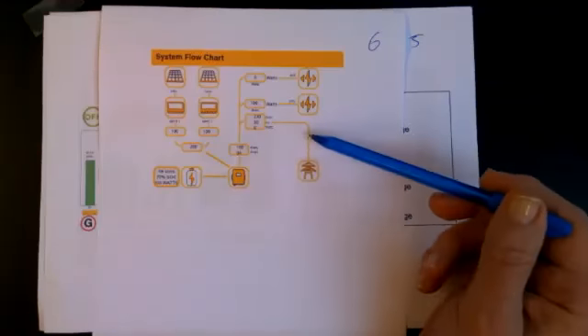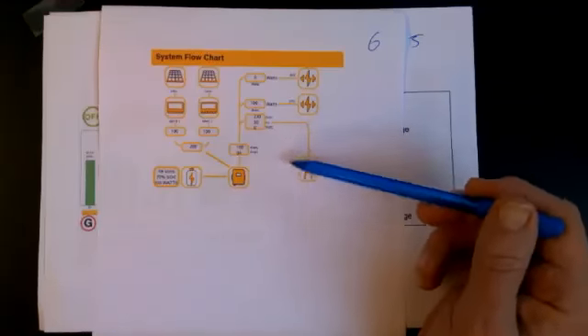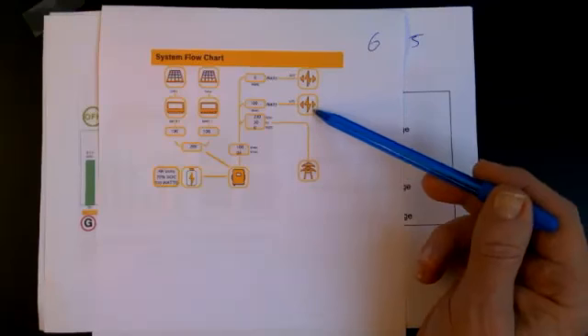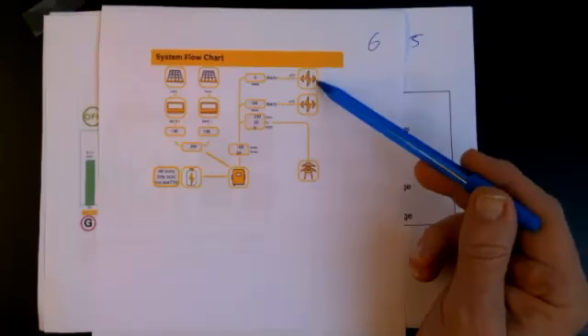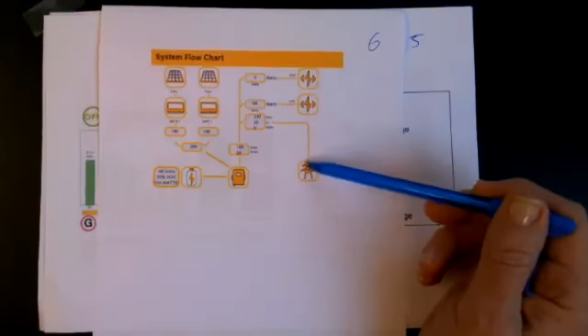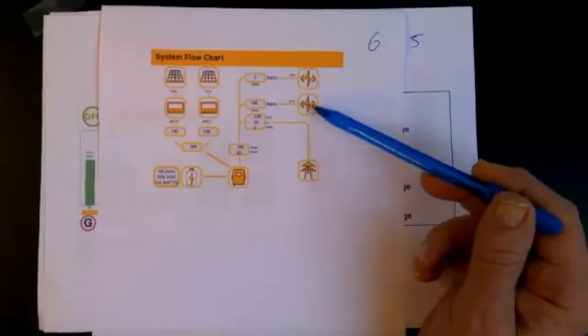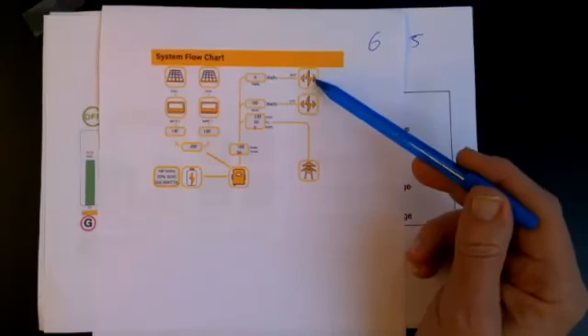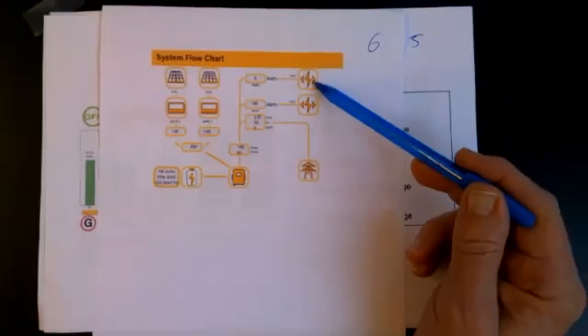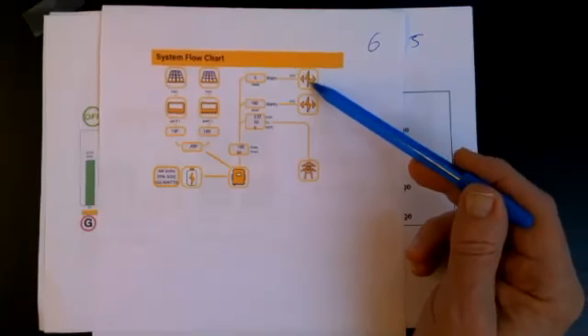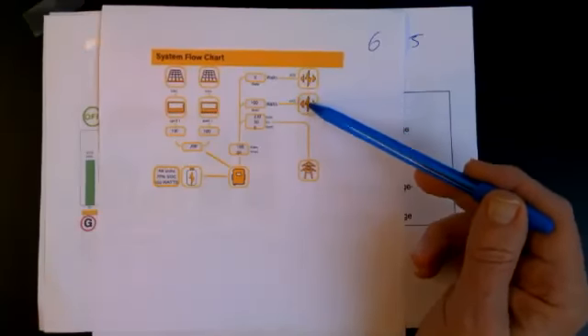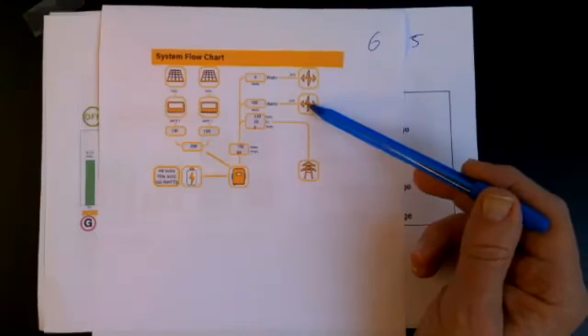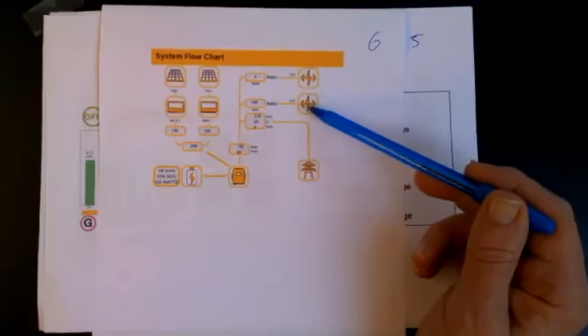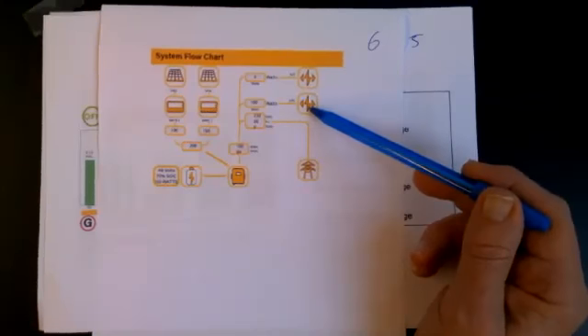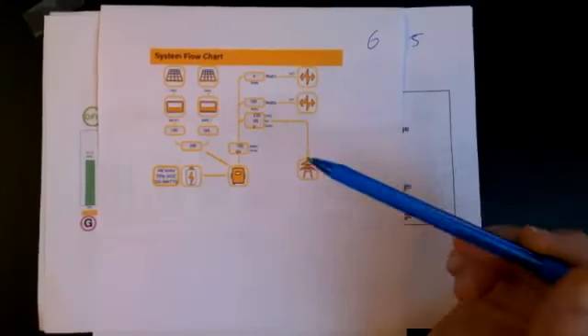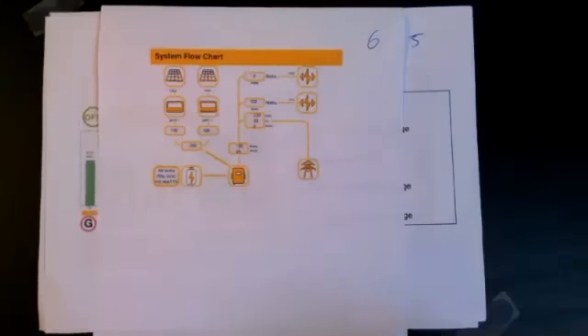You see here your three outputs, which is your grid connection, UPS, which is the load, and the auxiliary, which is the generator. It's worded slightly different here. So your grid, UPS, auxiliary. Auxiliary we call a generator, but it's actually an auxiliary, and it can do lots and lots of things. The UPS is a UPS load, uninterruptible power supply, which we call the load. So this is your essential loads, stuff you don't want to fail. And here is your grid.